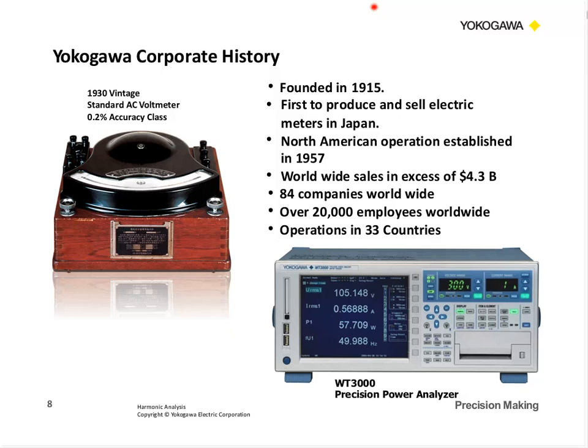It was an AC voltmeter, about a 1930s vintage, pretty good accuracy, 0.2% accuracy class. It's a moving coil type, has the mirror scale and the pointer. Come a long way since then with our precision digitizing instruments that we have now. I always say that then there was as much work that went into that wood case on that voltmeter as it did into the movement and everything else, because it's a real classic type of an instrument.